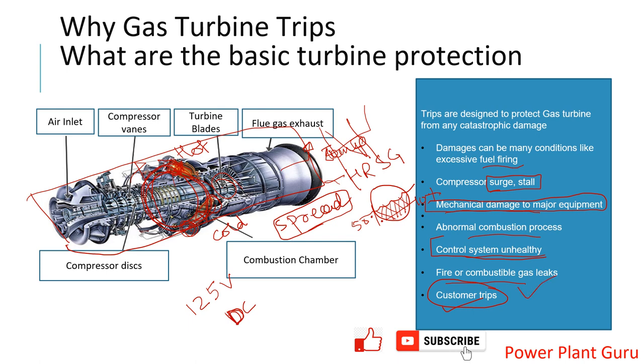Another example of a customer trip: if you are running a gas turbine supplying power to a process plant and that process plant trips, there is no requirement for power and you need to evacuate it — in that condition a customer trip also occurs. The key message is: whenever you are operating a machine or doing an investigation, think about why it has tripped and what protections are in place. If your machine is moving toward an unhealthy situation and not tripping, you need to take action and trip it manually to save it.